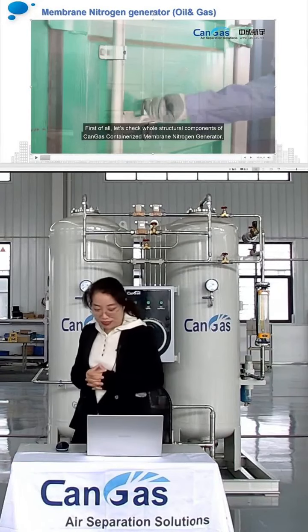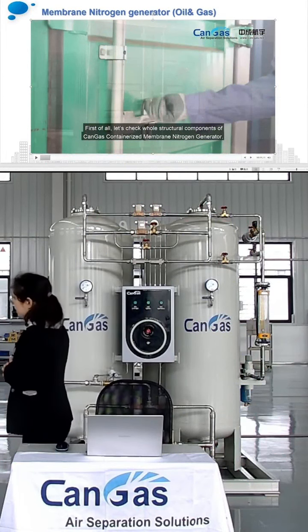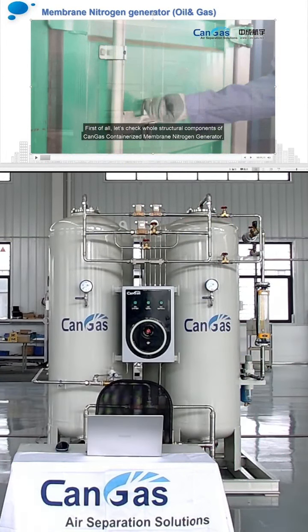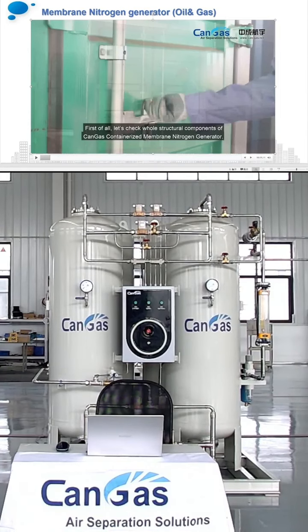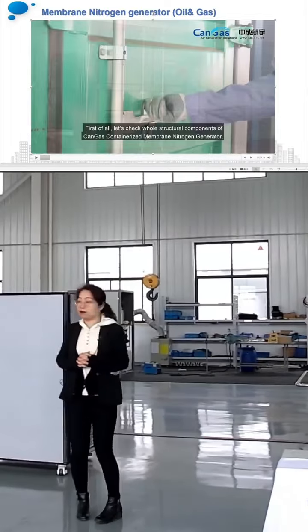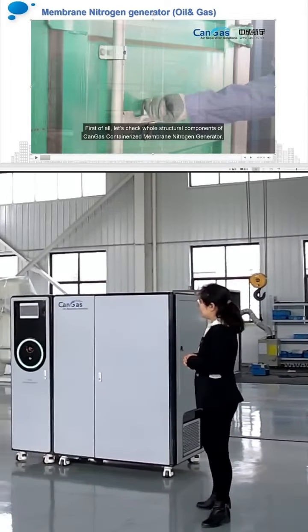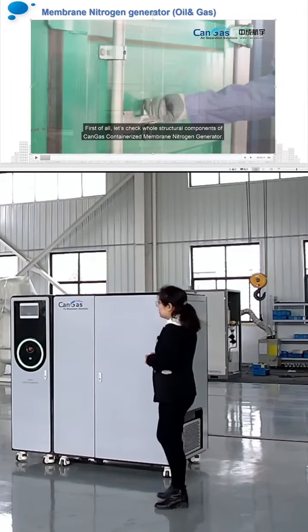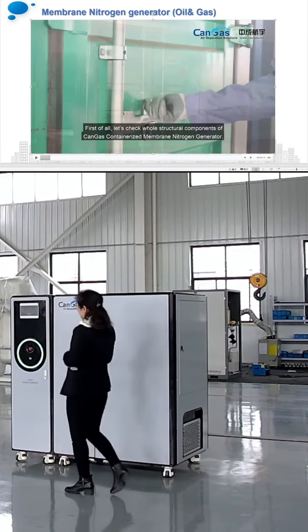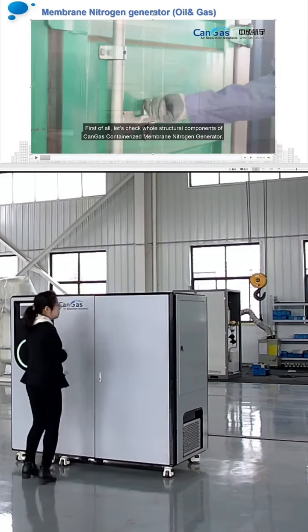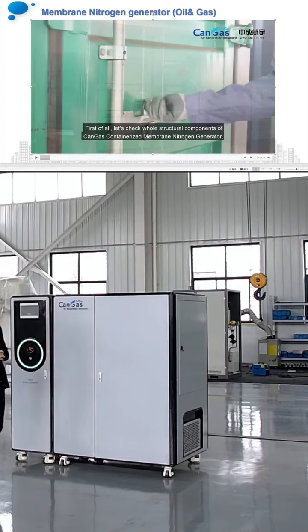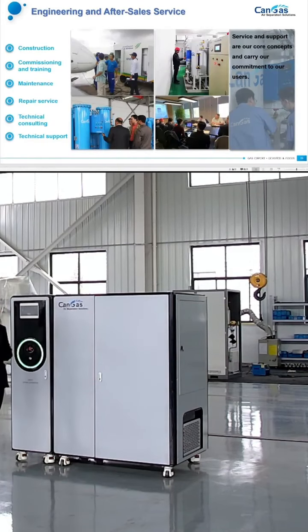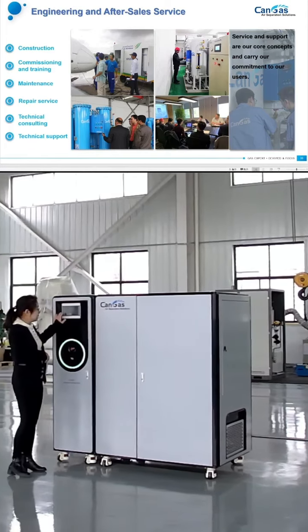Next, we can see our nitrogen generators, but it's a PSA nitrogen generator. It's only 12 cubic meters per hour. It's different from the membrane nitrogen generators. It's separated by the carbon CMS, carbon molecular sieve.